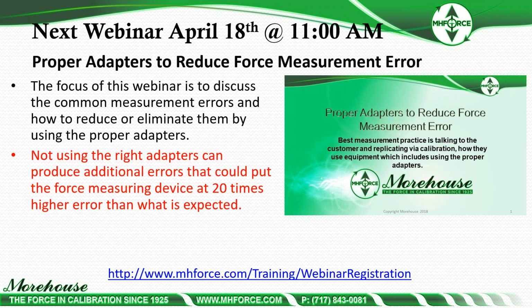Now, whether a lot of that error is just down in like 0 to 2%, that's what I'd like to know. I suspect that each load cell is going to be different. Alignment's going to be critical. And I also suspect that if you get everything right, the error is going to be minimized at below 10% of the range. But I would be very skeptical using a cell horizontally at low forces. I know one application is rocket thrust stands, which are used a lot in the horizontal position because they fire the rocket there, but they usually have a system that is fairly frictionless, and the errors are quite low. So maybe look at your system and see how alignment of everything is, see if there are any friction issues, see if everything can slide well in tension would be my suggestion.